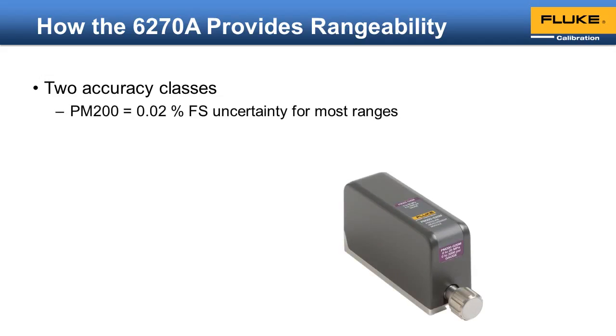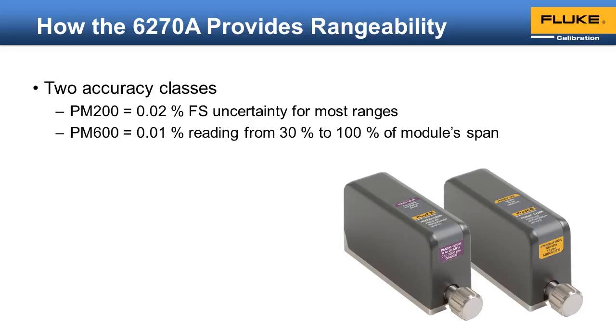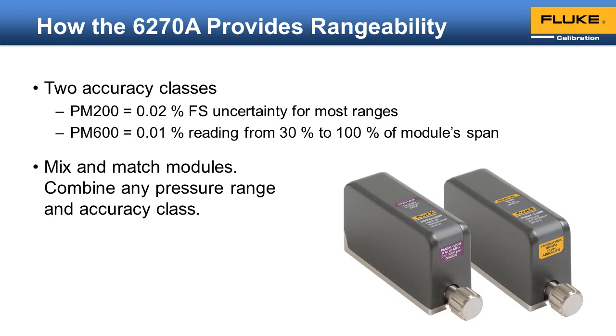The breadth of the measurement module offering is instrumental in providing true rangeability. The 6270A has over 30 modules to choose from, including 2 different accuracy classes and a variety of pressure ranges. The PM200 provides a 1-year specification of 0.02% full scale for most ranges, whereas the PM600 class provides a 1-year specification of 0.01% of reading for 70% of its span. This provides an unsurpassed level of rangeability. Flexibility brings rangeability. With the 6270A, you can mix and match modules as needed.